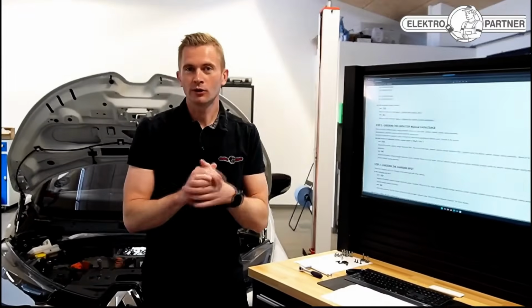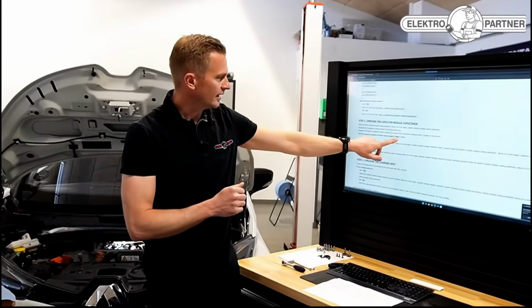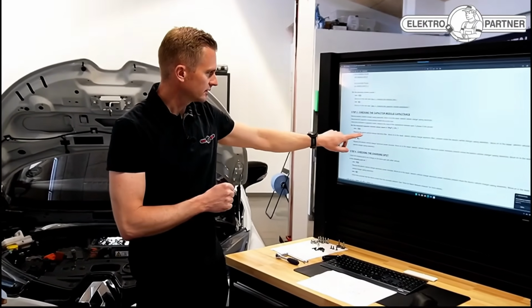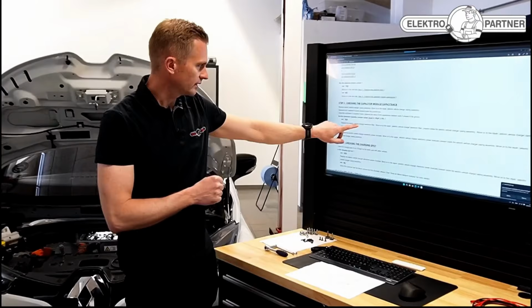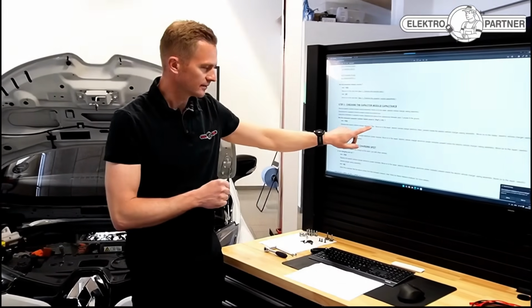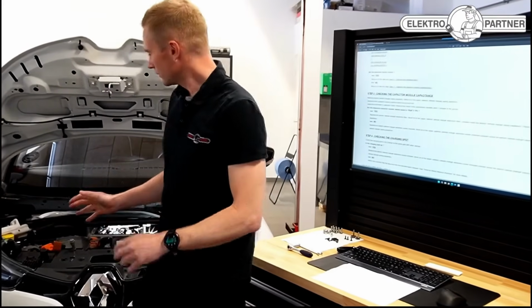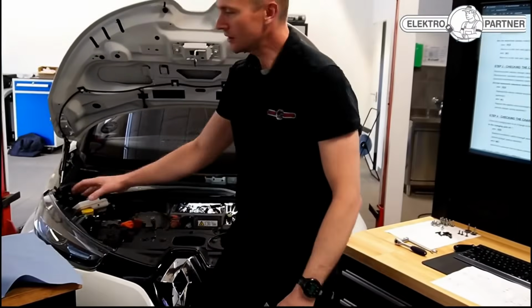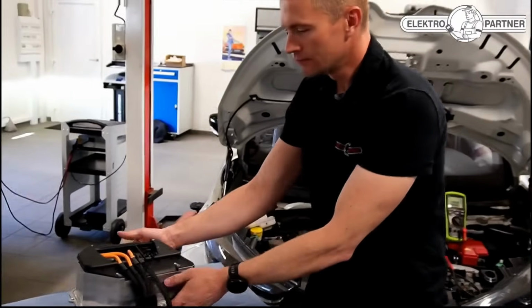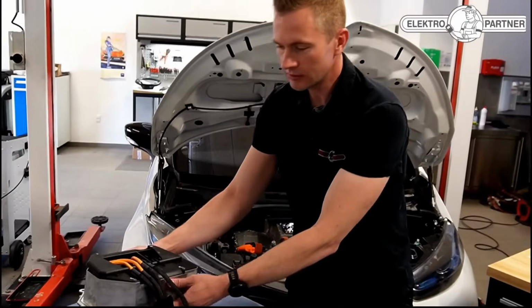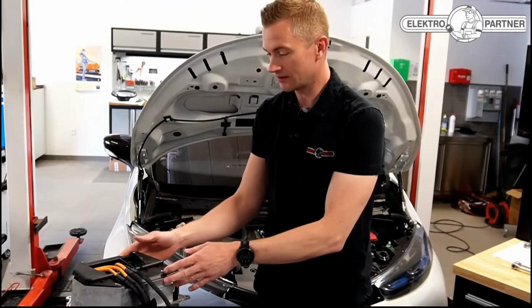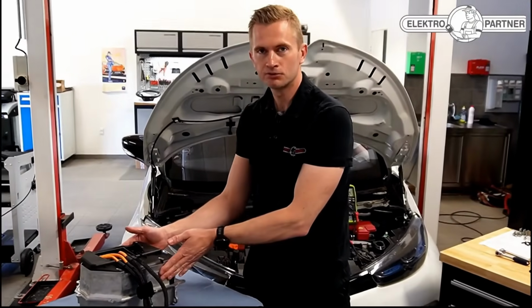So that means the measurements are within range, and if we say yes to that, then we need to replace the electric vehicle charger electronic filter. So we need to replace this noise filter which was sitting over here. We've already removed it and it's here now. According to the manufacturer's instructions, this measurement is enough to indicate that the fault must be inside this one.